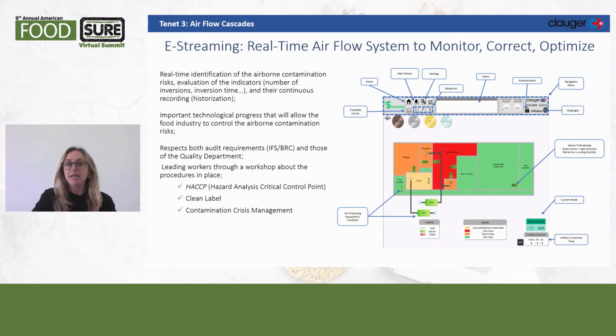To illustrate this system's efficacy, with one client we implemented the system, and they had 3 existing air handling units. We detected from the overall system that we could turn off 2 complete air handling units and just use 1 for proper pressurization and cascade through the facility. This resulted in significantly reduced operating costs and capital expenses they thought they needed.